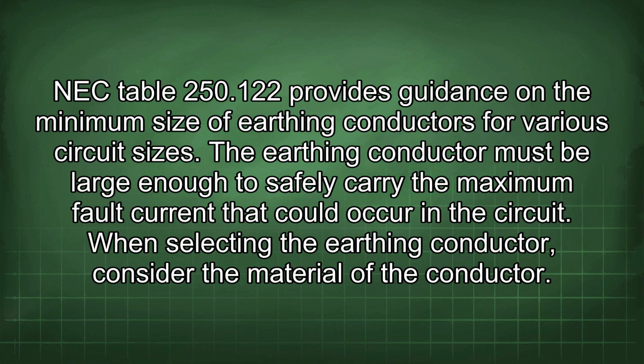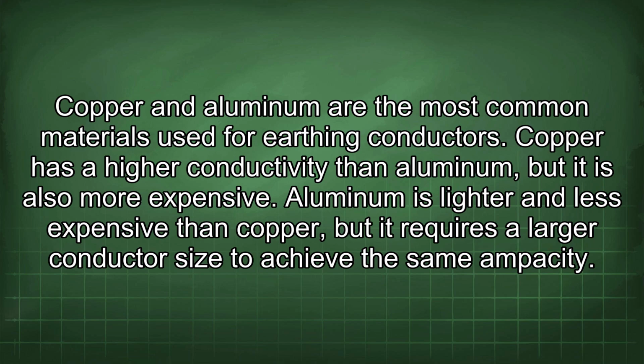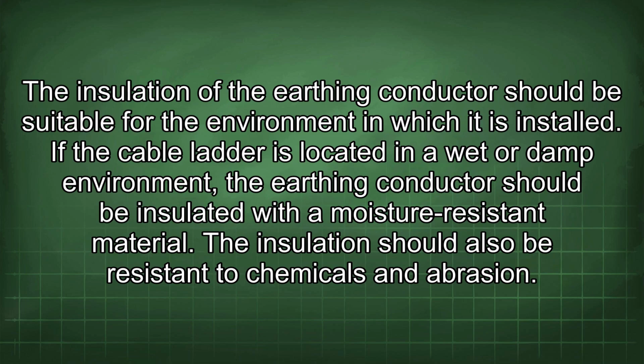When selecting the earthing conductor, consider the material of the conductor. Copper and aluminum are the most common materials used for earthing conductors. Copper has a higher conductivity than aluminum, but it is also more expensive. Aluminum is lighter and less expensive than copper, but it requires a larger conductor size to achieve the same ampacity. The insulation of the earthing conductor should be suitable for the environment in which it is installed. If the cable ladder is located in a wet or damp environment, the earthing conductor should be insulated with a moisture-resistant material. The insulation should also be resistant to chemicals and abrasion.